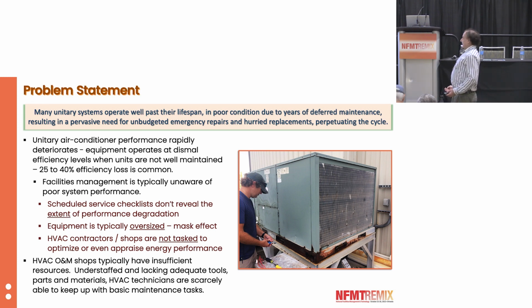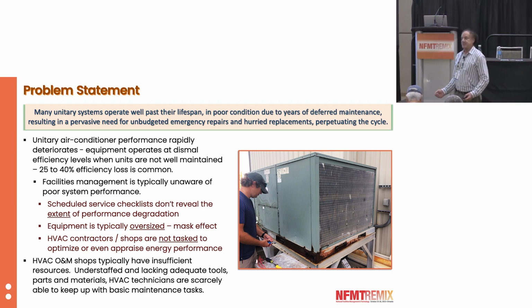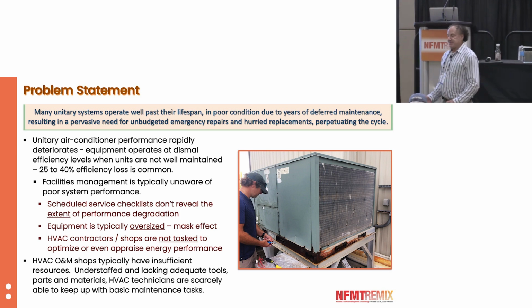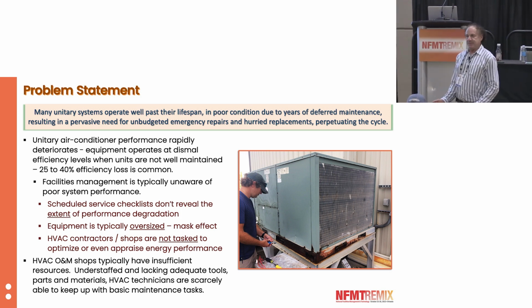provide cooling because they're often oversized, for redundancy. So when the size is selected, usually it's an extra 50% or even twice what the load is. So let's say you have a package unit that's got two compressor circuits. It's sized so that if one compressor fails, the second compressor maybe can't take the whole load, but can at least keep people from really screaming.